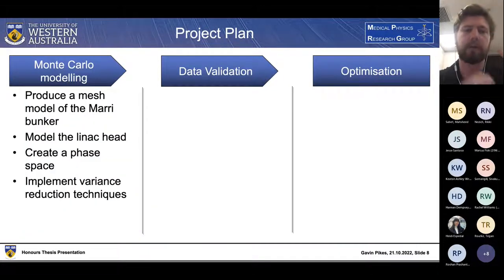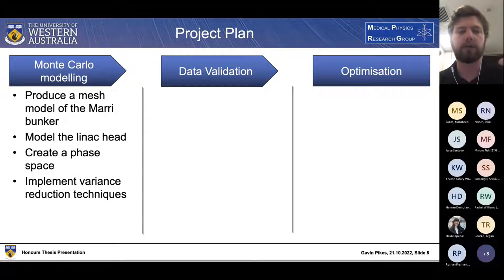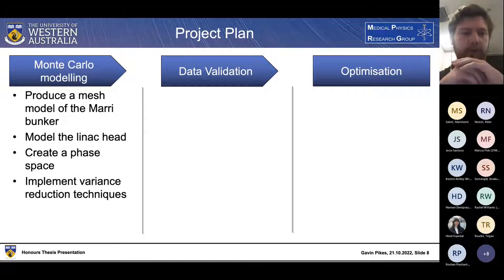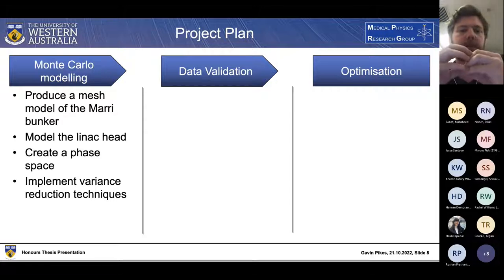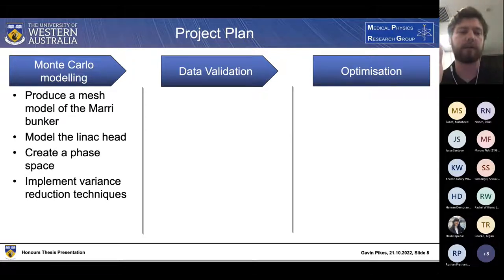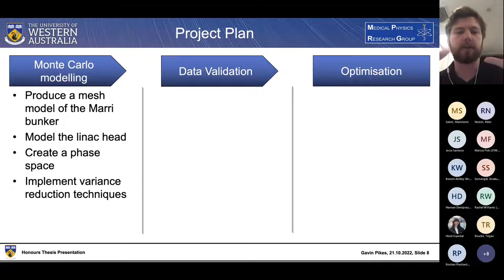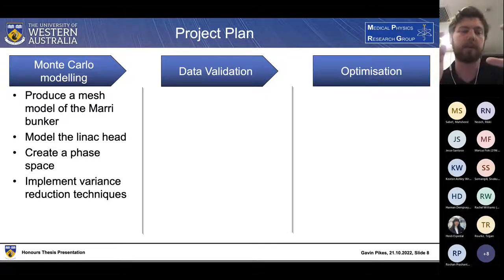My project plan has three main components. The first is the Monte Carlo modelling stage: producing a mesh model of the Marri linac bunker using the floor plan, then producing a model of the linac head with all its major components to simulate a holistic beam, and then storing the beam as it leaves the linac head in a phase space file. This stores the energy, direction, and particle type of particles impacting that plane to a file, so we can sample from it when simulating the bunker itself, cutting down on computational time significantly.